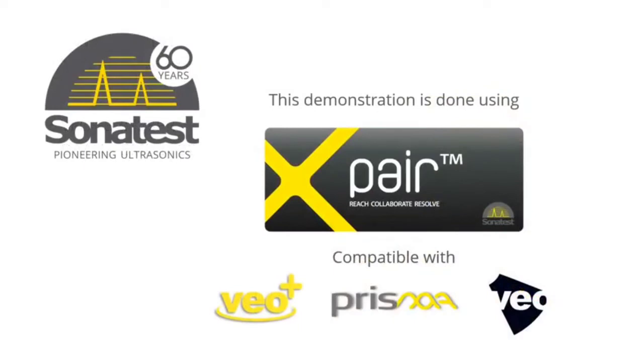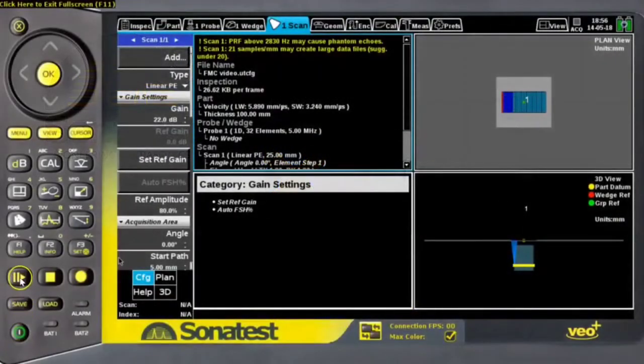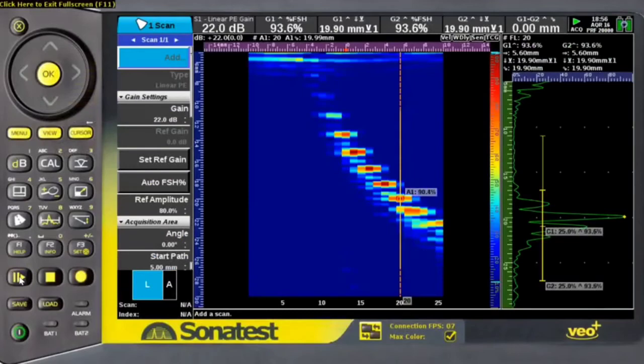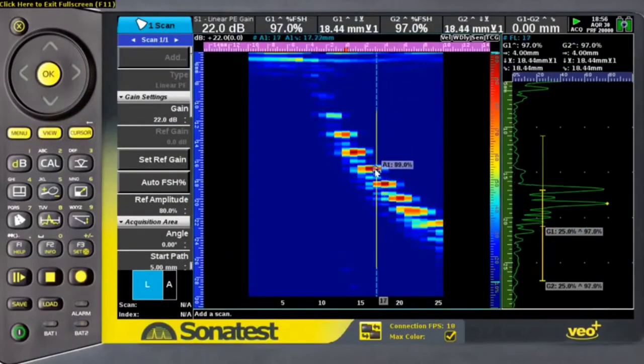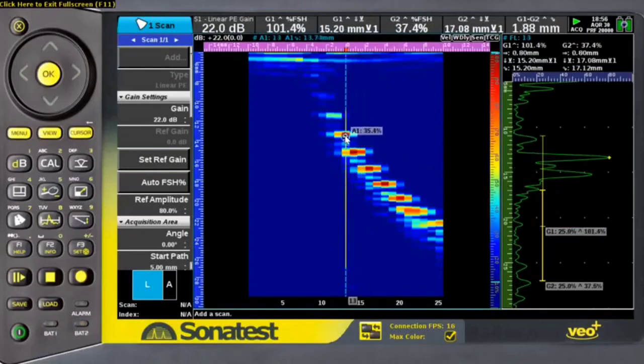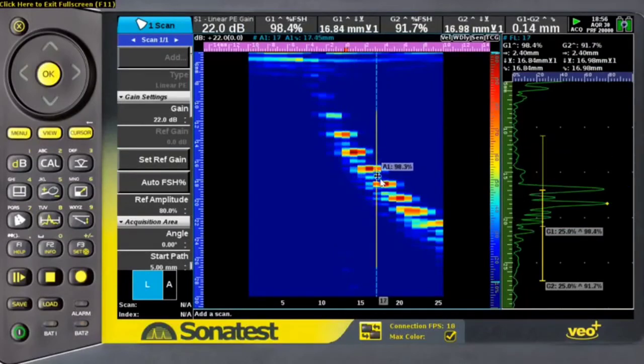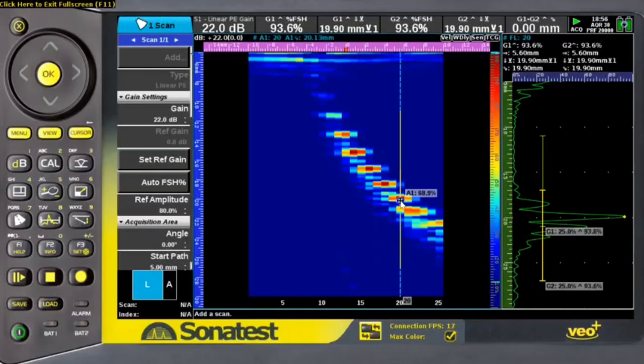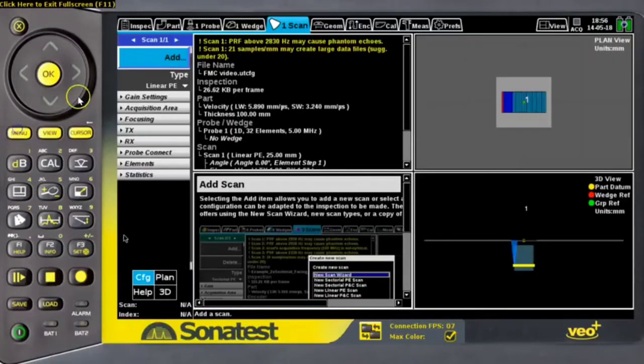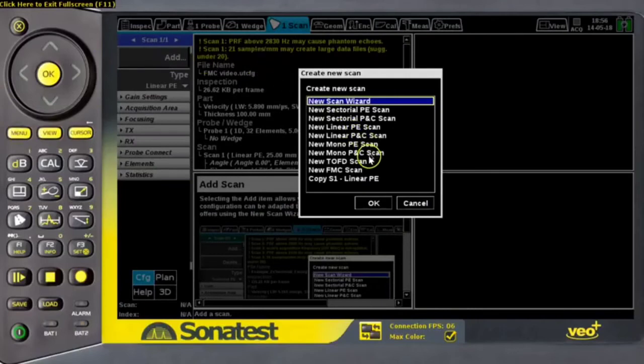Also, all the screen capture of the instrument in this video have been performed using the XPair software from Sonatest, the remote control solution. Now, starting my instrument, I already prepared a linear scan over the sets of defect. As you can see, we see all the SDHs underneath the probe. Now, because my instrument has the FMC TFM software option on it, I'm able to create a new FMC scan on my instrument.